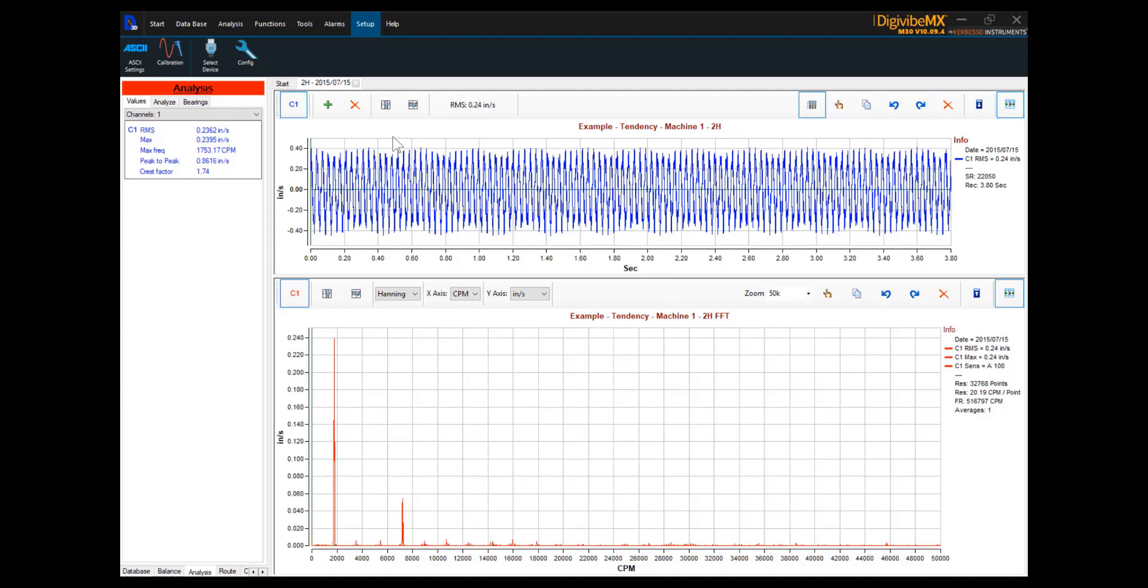And then, if anything is detected in the lower resolution reading that suggests a potential problem, they may go out and take a second data collection on that specific piece of equipment that will take longer but will give a higher resolution FFT for further analysis.